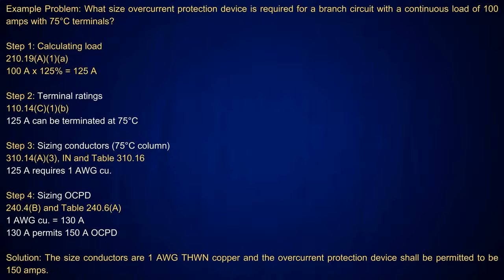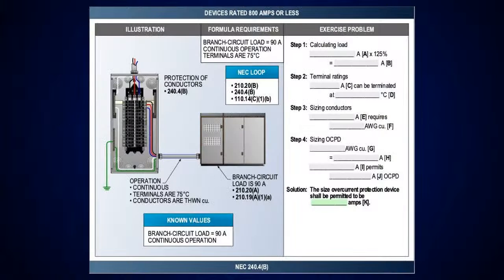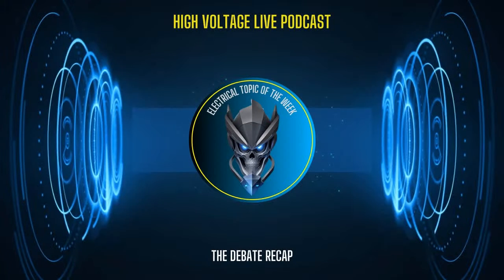Now, let's look at this a little bit further. Could I put 100? We'll just leave that. We'll just leave it at 150 amps. Okay. Here it is. I've got 90 amps. It's continuous. I take it at 125%. Then you size your overcurrent protection device and conductors based on whatever the calculated amperage is. That's for your homework. And that gets us through all of the calculating conductor ampacities. And we'll do the homework next week. And then we're going to start on sizing overcurrent protection devices.